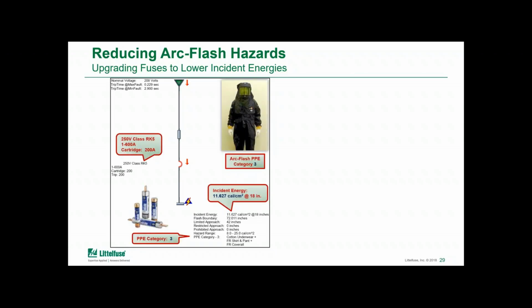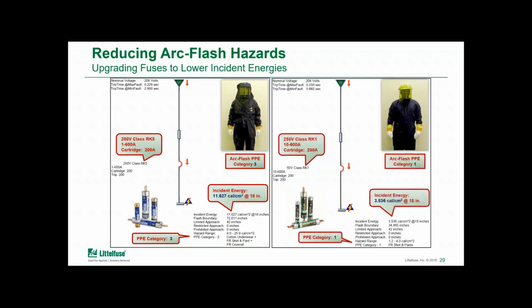Here in the one line diagram, we can see that for the RK5 200 amp fuse rating, the incident energy was calculated to be 11.6 calories per centimeter squared. Relating that to the PPE categories available, that would be a category 3. By comparison, if you upgrade to an RK1 200 amp fuse, which is physically the exact same size, so it should not require a change out of fuse blocks or fusible disconnect switches, the incident energy calculates to 3.5 calories per centimeter squared, and with that, a PPE category of 1.